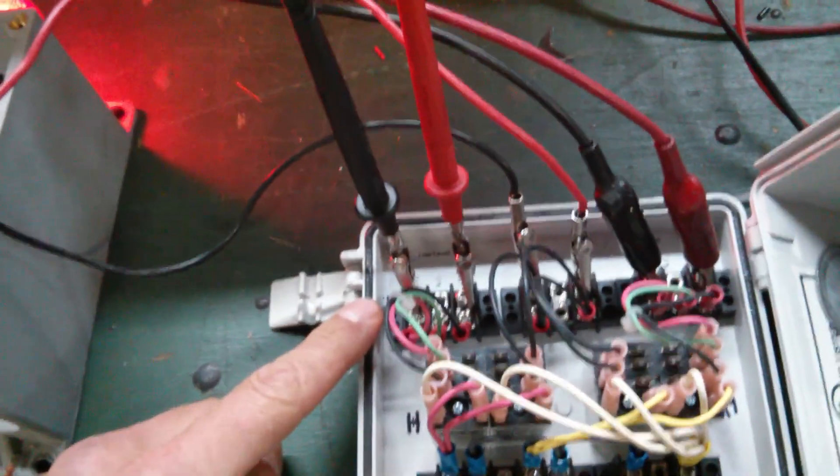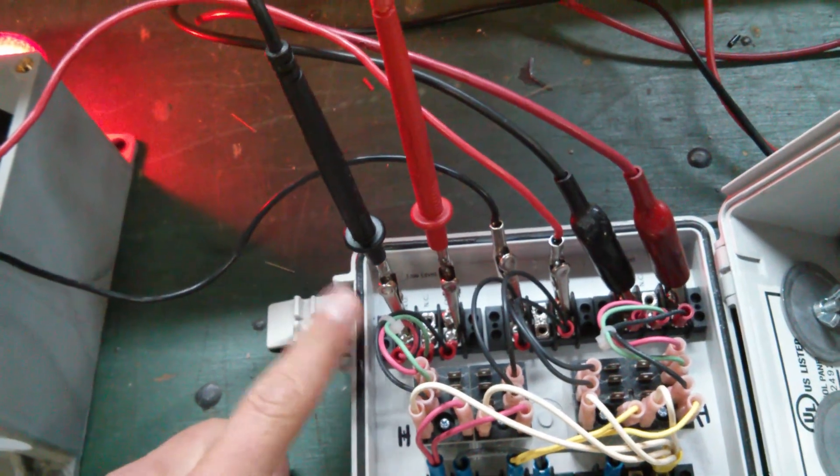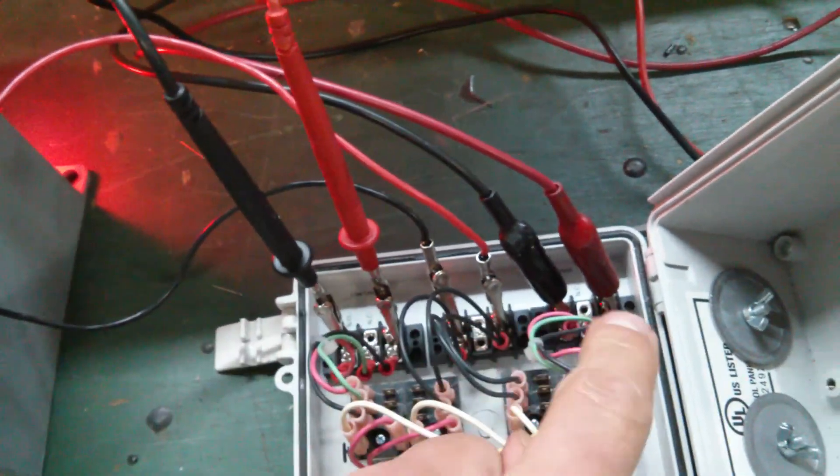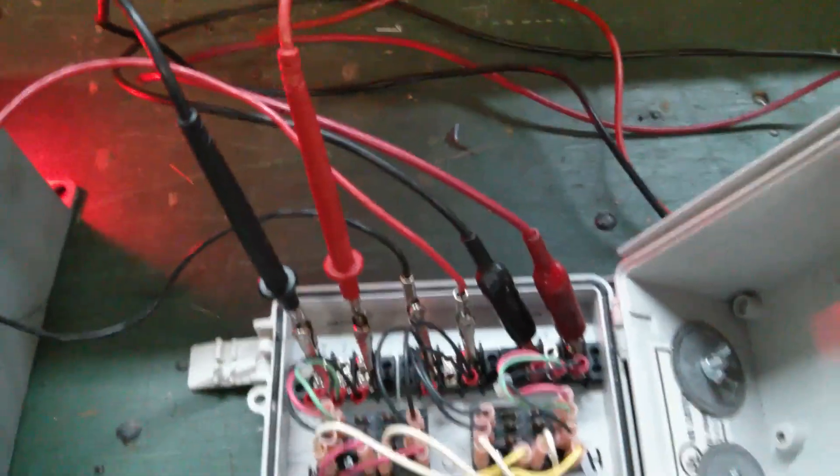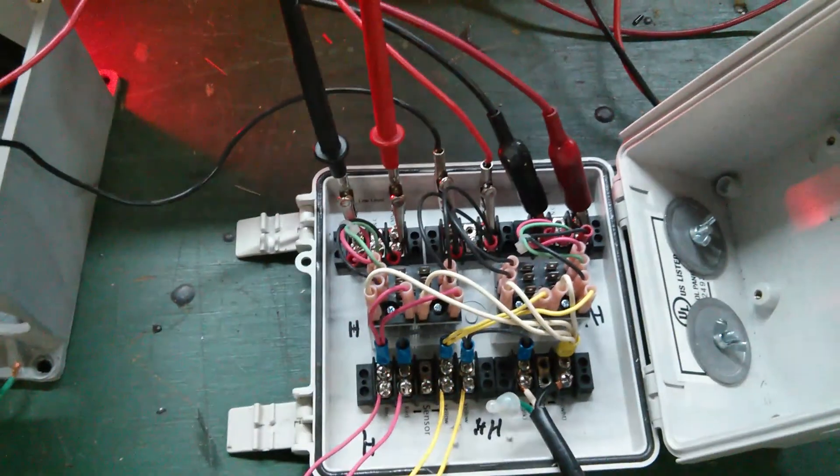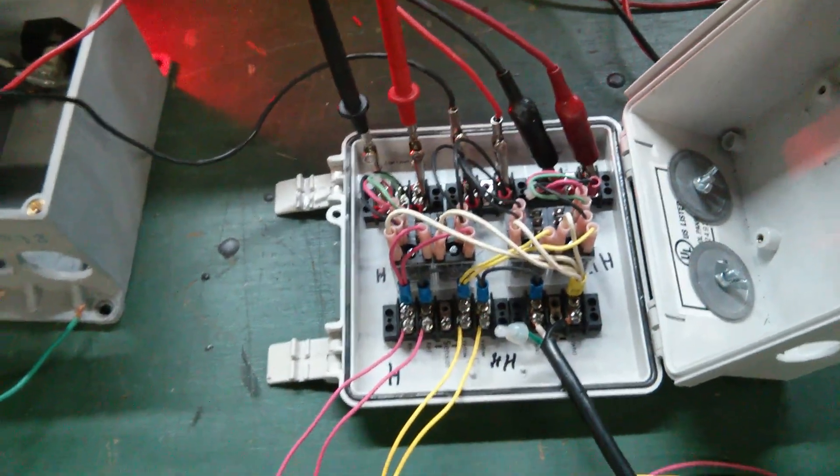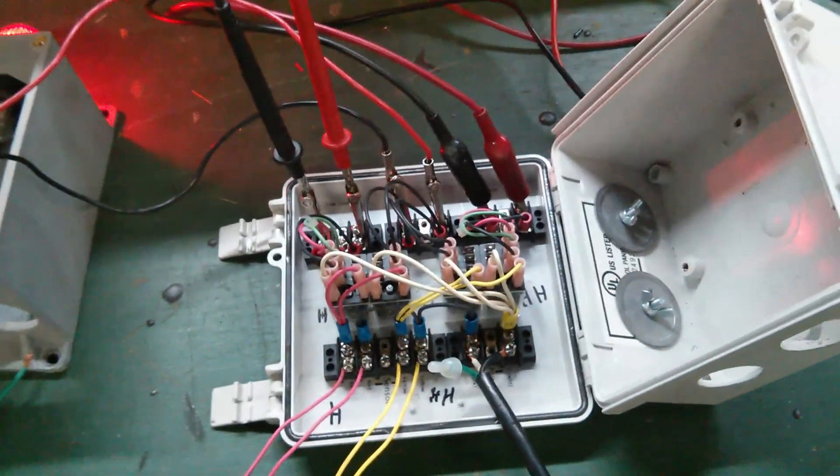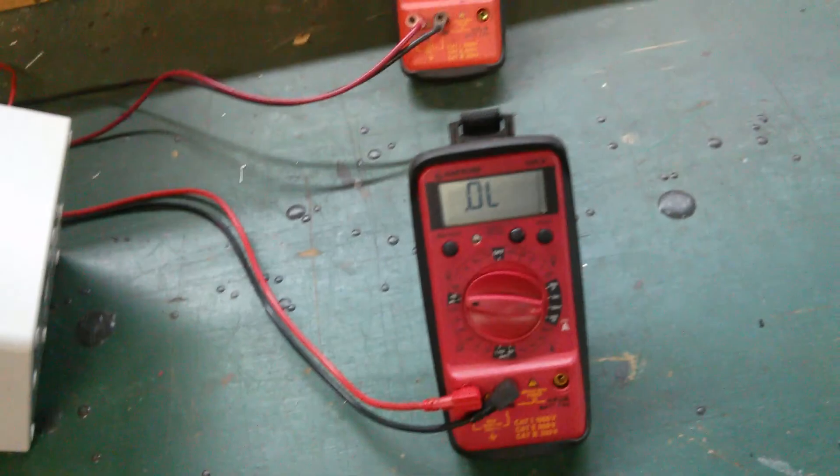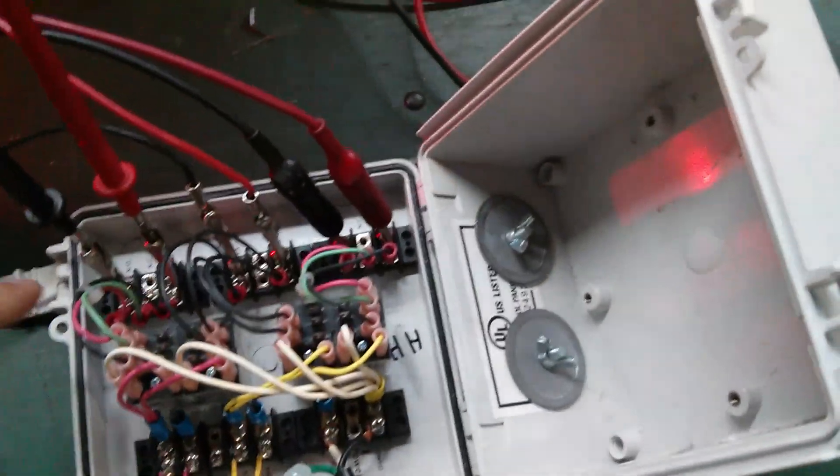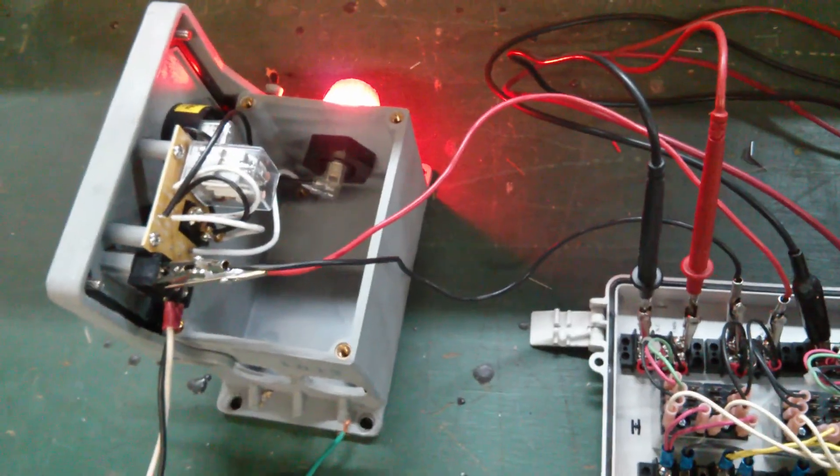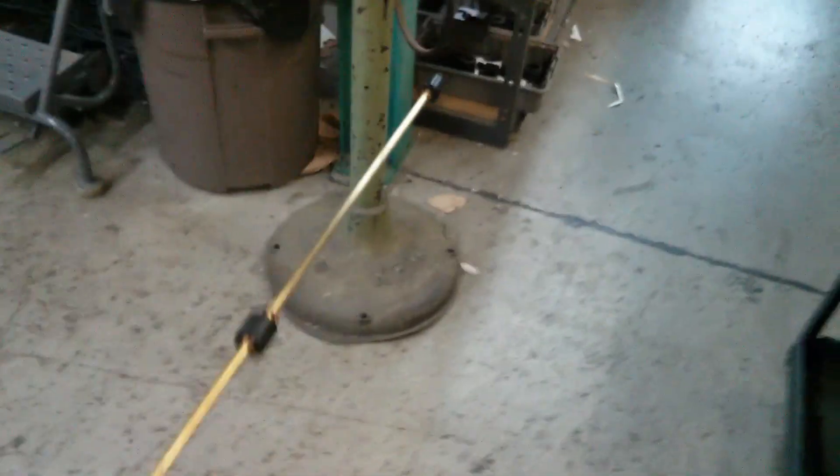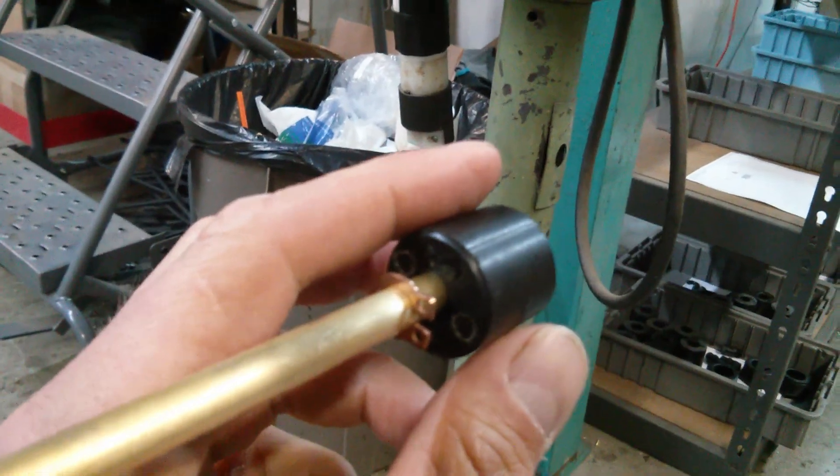So that's a dry contact relay output right there. Two, one for low, one for high. You can go to your fire alarm panel and it's a dry contact, so it's either open or closed. I have them on the opens, but you can wire to the closed if you need it.